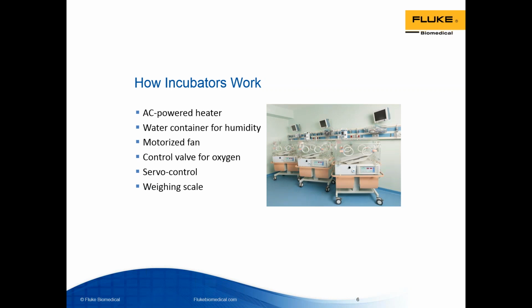The incubator may include an AC-powered heater, a water container to add humidity, a motorized fan to circulate the warm and humid air throughout the cabin, a control valve through which oxygen might be added, and then a servo control to help regulate air temperature. So a temperature-sensing thermistor is actually taped to the infant's abdomen. There are hand access ports with doors that limit the introduction of cooler air while the infant, if it needs to be handled, and the hood or the side panel can be opened to gain greater access to the infant.